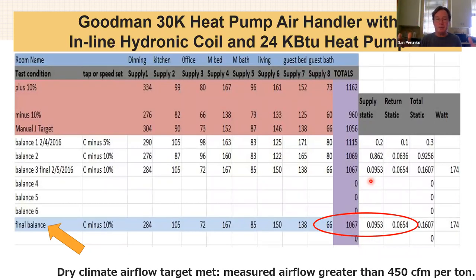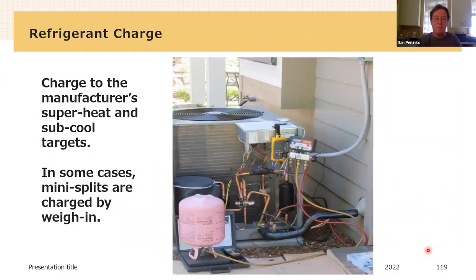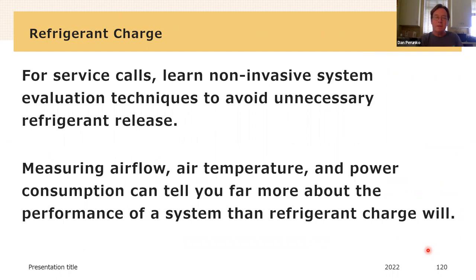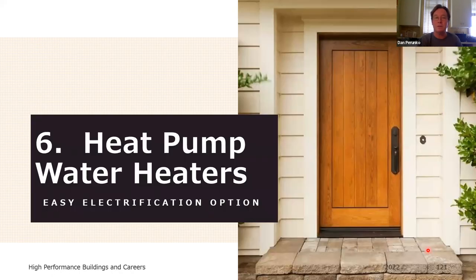And then you have to commission these things, right? So this is our worksheet that we actually do on every system. This is all of the rooms in the house, target airflows, our measured airflows, total airflow, static pressures and power consumption, all recorded and compared against the metrics that we had in earlier slides. And then refrigerant charge looks like this. Whenever possible, if we don't have to hook up to the refrigerant system, we shouldn't, right? Every time we hook up to the refrigerant system, we release refrigerant. So learning how to measure airflow, power, temperatures, and seeing if the system is working properly with those metrics allows you to diagnose the system without testing refrigerant charge.